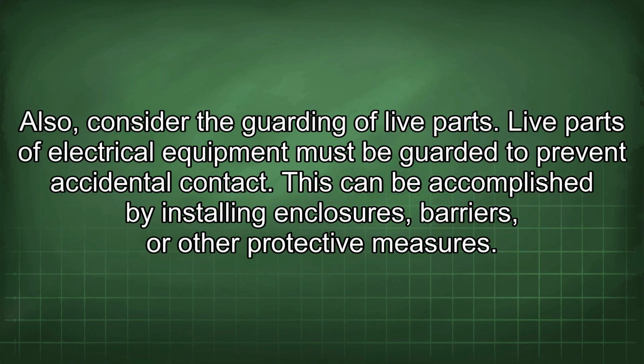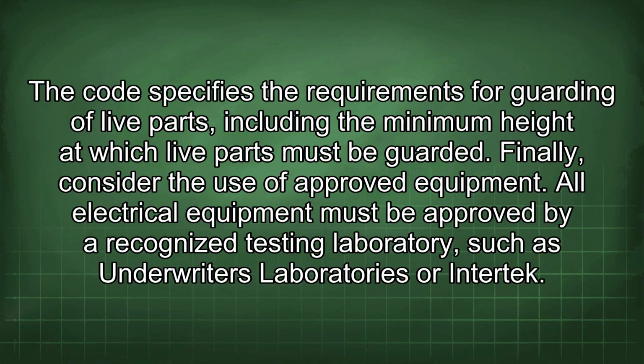Also, consider the guarding of live parts. Live parts of electrical equipment must be guarded to prevent accidental contact. This can be accomplished by installing enclosures, barriers, or other protective measures. The code specifies the requirements for guarding of live parts, including the minimum height at which live parts must be guarded. Finally, consider the use of approved equipment.